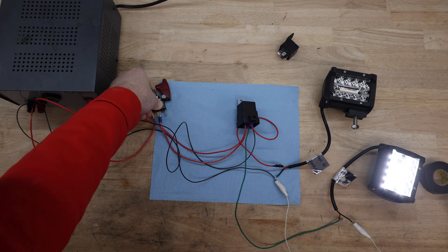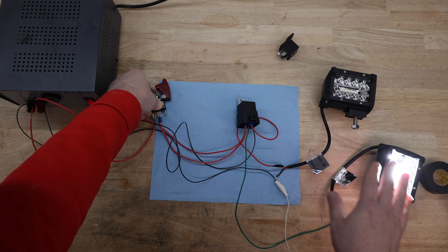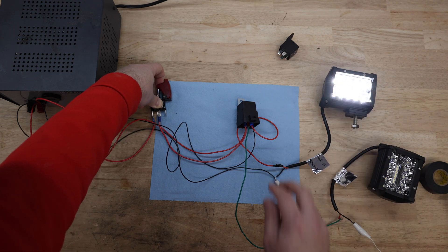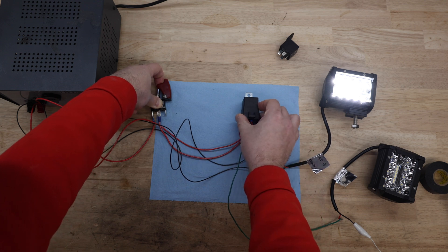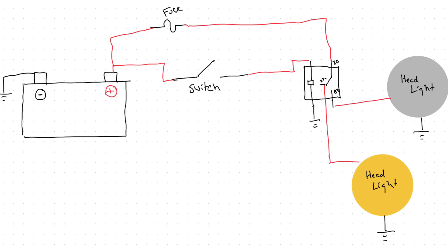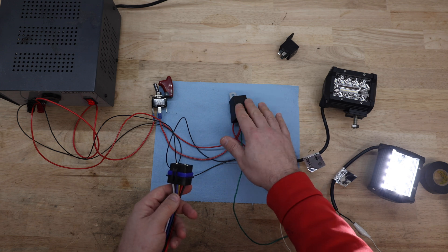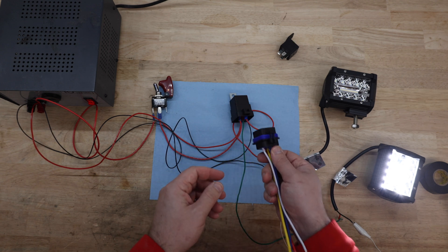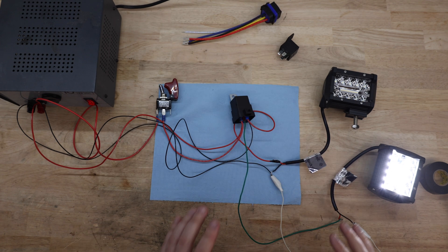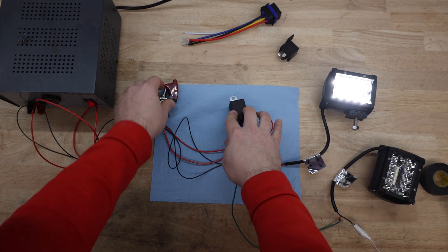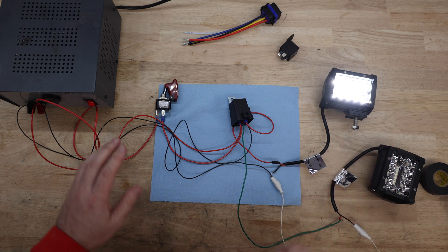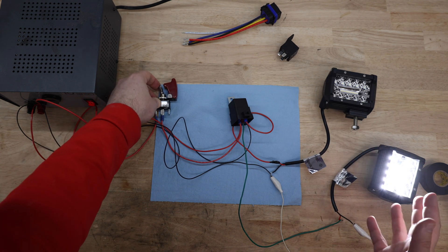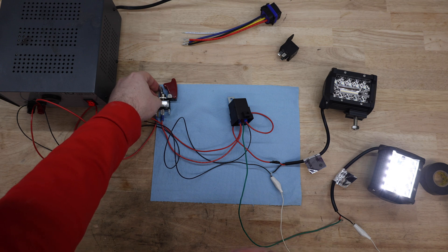When you have it off this one is on. When you have it on 87 turns on. So this relay is a single pole double throw relay. I'll also put the diagram of how it's wired up here so you can see it on the screen. This is a simple relay that I'll also link below and it comes with this waterproof connector here. Now the place where you want to use a relay like this is when you have two independent systems where you never want them to be operating at the same time. It's used a lot in controls and you also see it used for some motors.